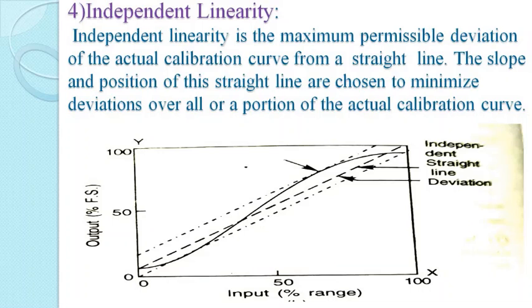The fourth type is independent linearity — the maximum permissible deviation of the actual calibration curve from a straight line, where the slope and position of the straight line are chosen to minimize deviation over all or a portion of the actual calibration curve. Here the calibration curve is not dependent on a straight line, so the deviation on both sides is different — one side is minimum and the other is maximum. The diagram shows how linearity is independent of the straight line deviation.